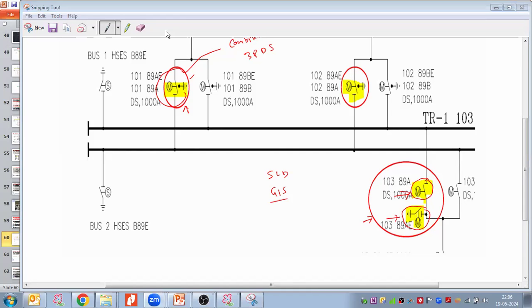Yes, that's fine, the disconnector and earthing switch together. It could be together at a high voltage level as well, and it is good because interlocking is easily possible. So what I am saying is that you check with the manufacturer, and if they have the combined arrangement, then it's good. You can take that arrangement. Okay, Santosh.